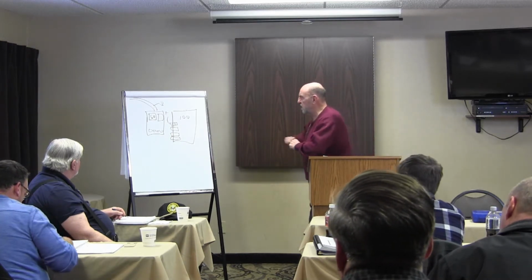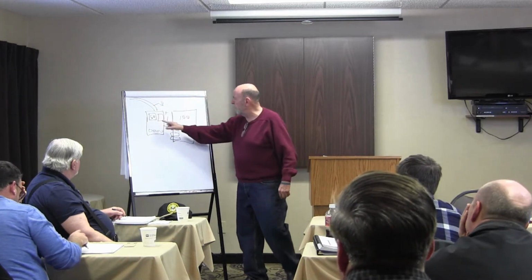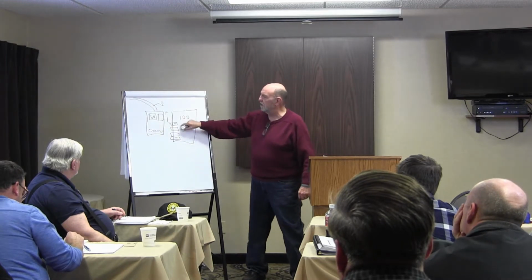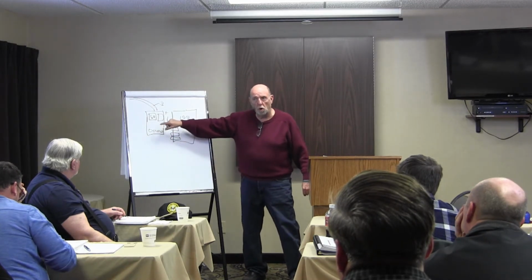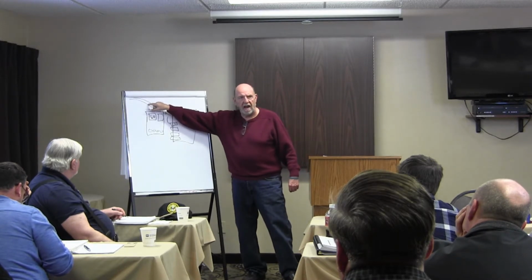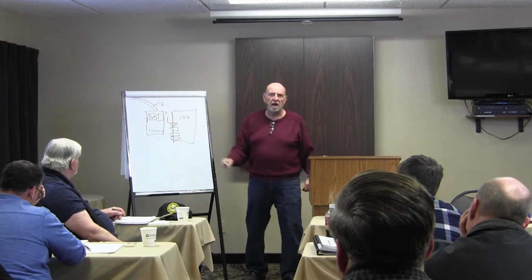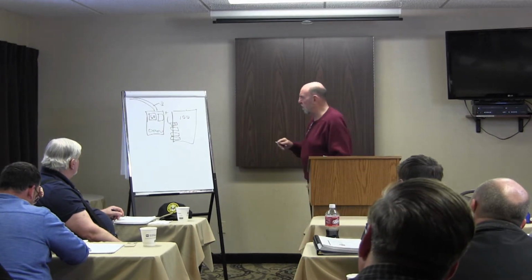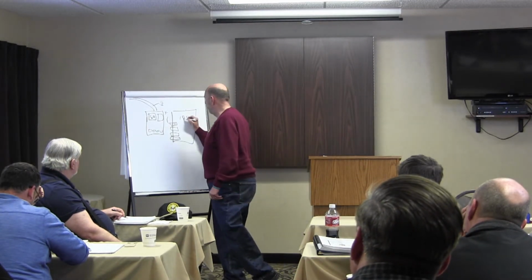Any questions so far? Just remember, when you see a 60 amp, you used to have a fuse system. So if you do see a box that looks like it had a fuse, or you walk into a fuse box, just be cognizant of the fact that that wire may not be a 100 amp or 150 amp breaker.